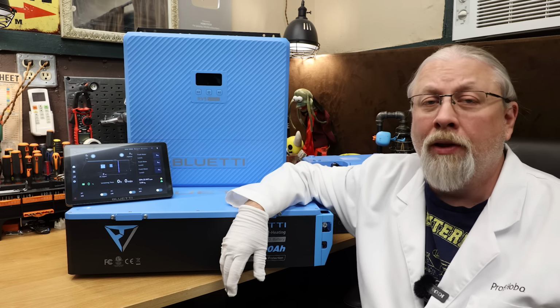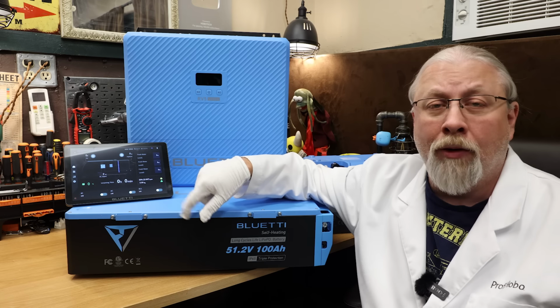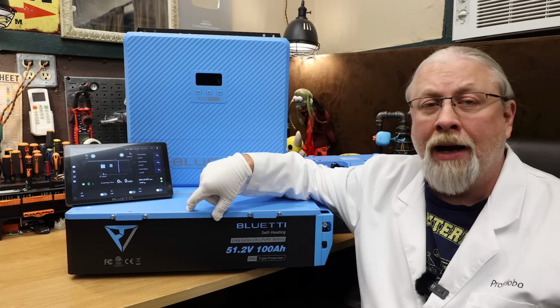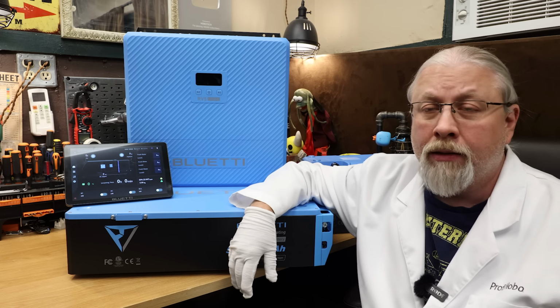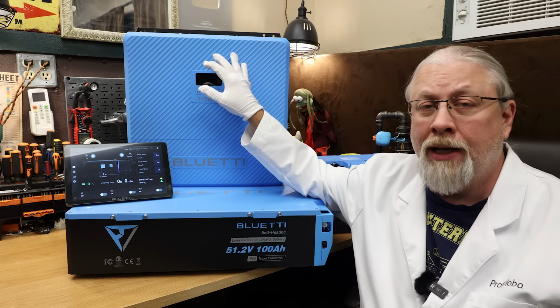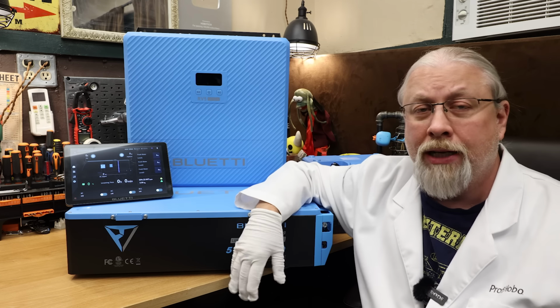Note that I scored 4.3 kilowatt hours running the inverter, and 4.6 kilowatt hours actually came out of the battery. That means the inverter only wasted about 300 watt hours, or around 6% of the usable capacity during that test, which is actually quite good.